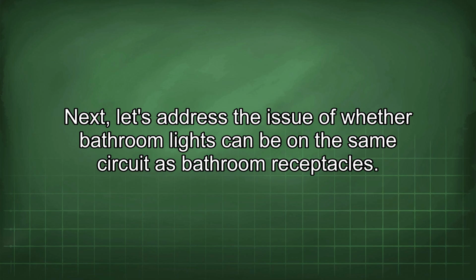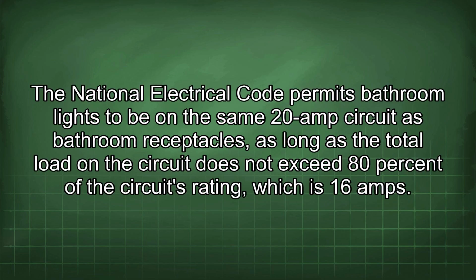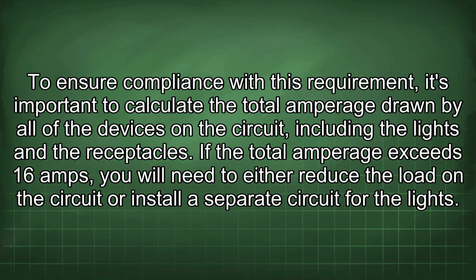Next, let's address the issue of whether bathroom lights can be on the same circuit as bathroom receptacles. The National Electrical Code permits bathroom lights to be on the same 20 amp circuit as bathroom receptacles as long as the total load on the circuit does not exceed 80% of the circuit's rating, which is 16 amps. To ensure compliance with this requirement, it's important to calculate the total amperage drawn by all of the devices on the circuit, including the lights and the receptacles.